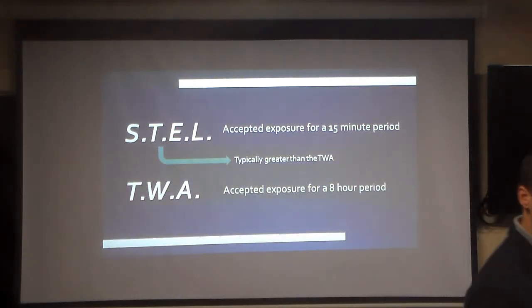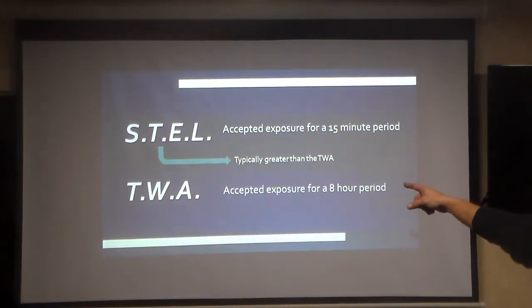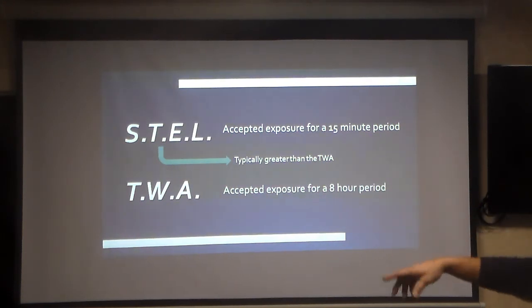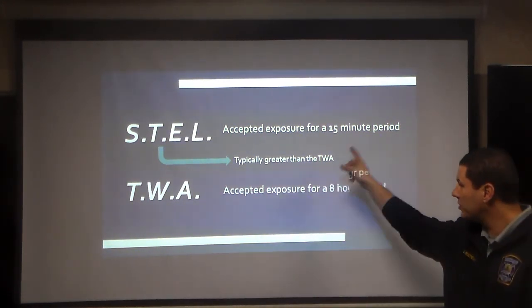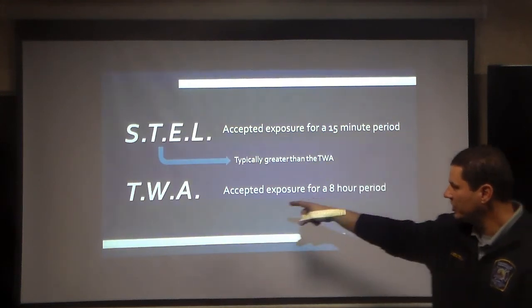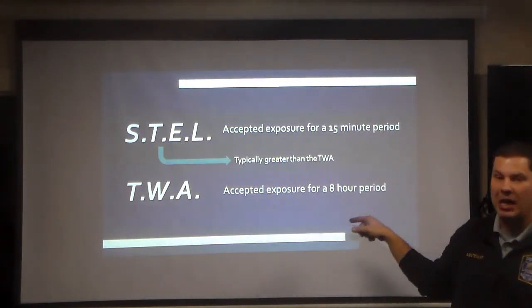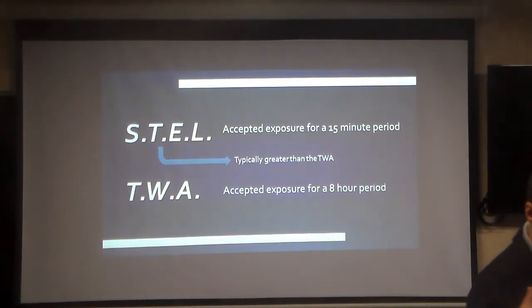As it's going through the cycles, you'll see where it says short-term exposure limit and the minimum alarms. The short-term exposure limit is a 15-minute exposure. The TWA is the time-weighted average, for an 8-hour period. So those are two of the different types of alarms that could occur on this meter: short-term at 15 minutes, and time-weighted average at 8 hours.